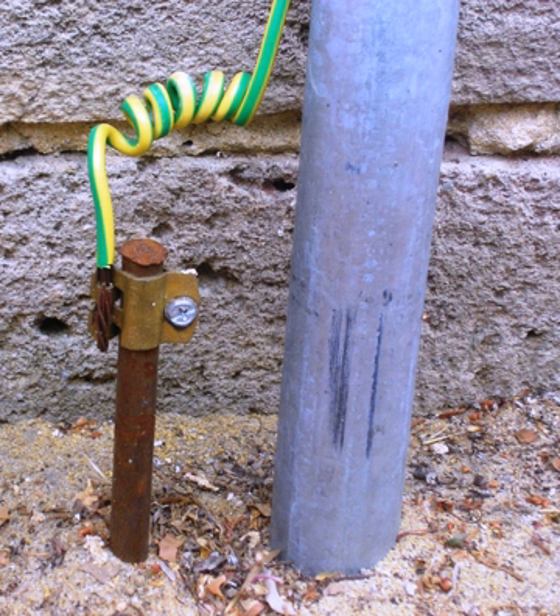Topic: Impedance grounding. Distribution power systems may be solidly grounded, with one circuit conductor directly connected to an earth grounding electrode system. Alternatively, some amount of electrical impedance may be connected between the distribution system and ground, to limit the current that can flow to earth. The impedance may be a resistor, or an inductor coil.